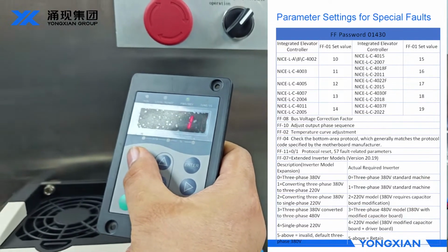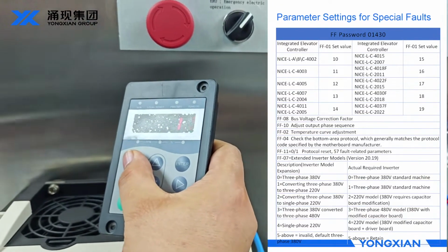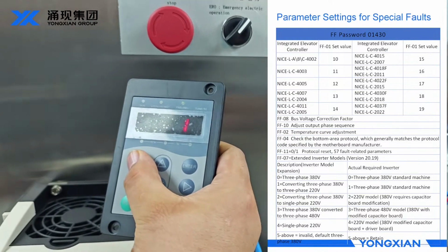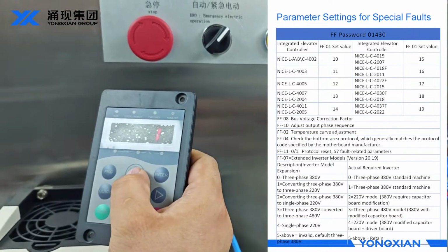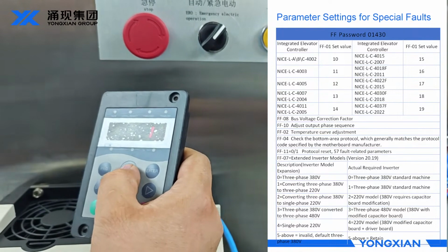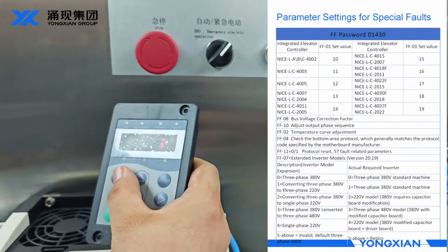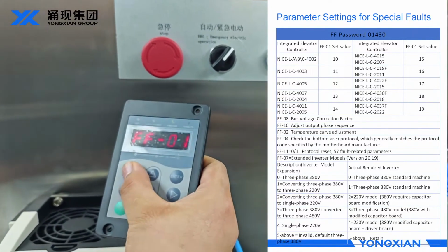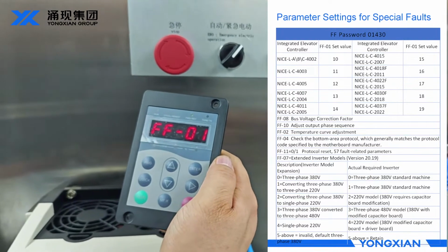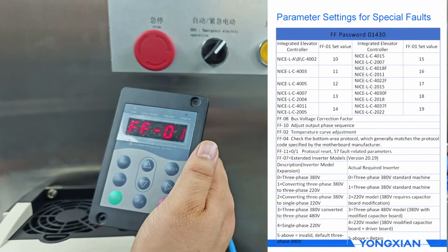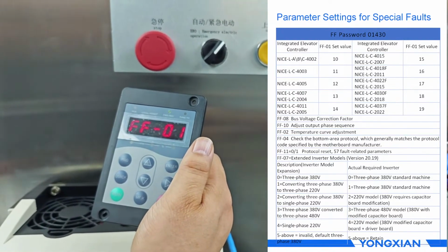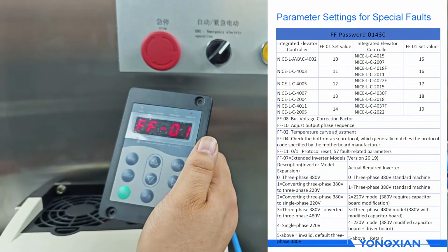Let's see. If you have a NICE L-C-4002, we set FF01 to 10. If it is NICE LC4003, we set 11. For LC4005, we set 12.